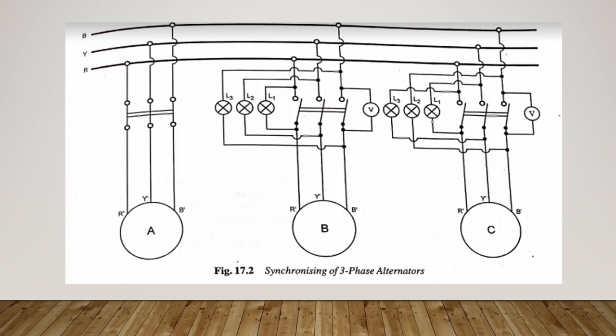So in this figure we can see that alternator A is supplying a load with alternator B ready to start. If these are low voltage alternators, alternator B can be phased out by connecting three lamps across the ends of the triple pole paralleling switch. Like this, these are the triple pole switch. The prime mover of the incoming alternator B will be started and brought up close to the rated speed. The alternator is then excited and its voltage is raised by increasing the excitation to that of the running alternator or bus bars, and the lamps will be watched closely.